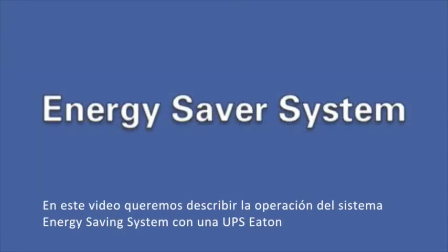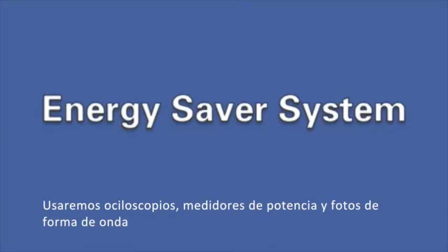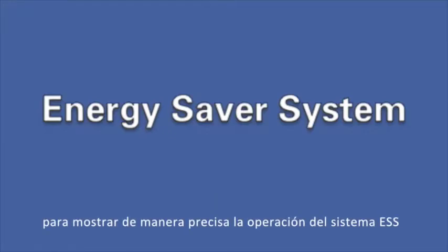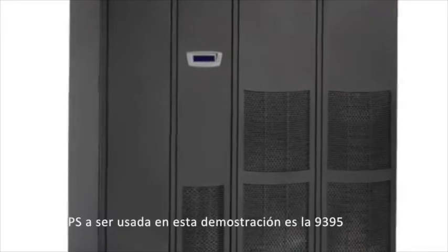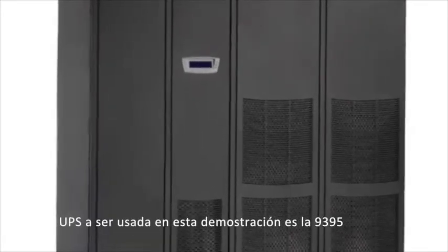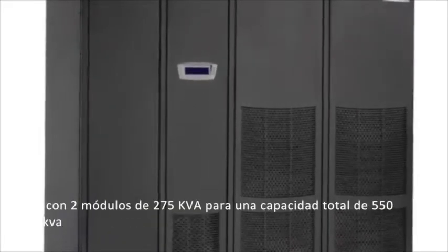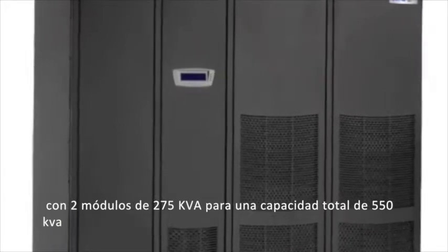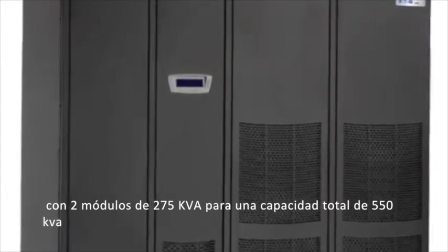In this video, we want to describe the operation of the energy saver system with the Eaton UPS. We'll be using oscilloscopes, kilowatt meters, and waveform capture to accurately show the operation of the energy saver system. The UPS system we'll be using for this demonstration is a 9395 series with two 275 kVA modules for a total capacity of 550 kVA.